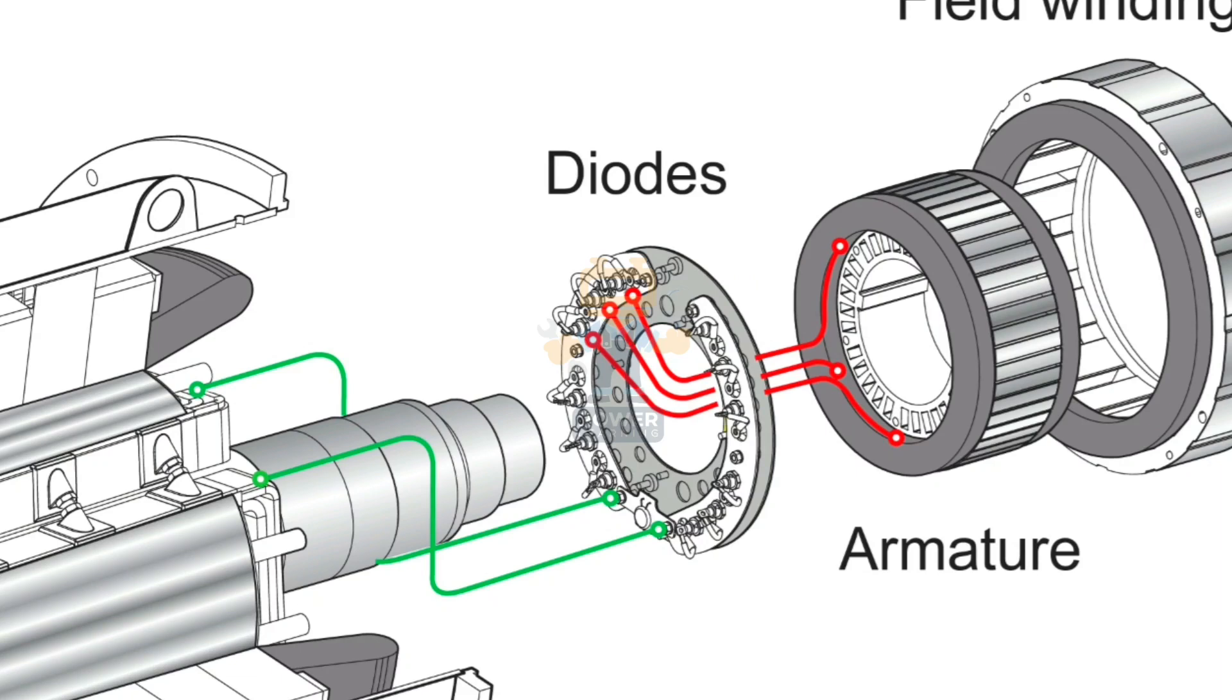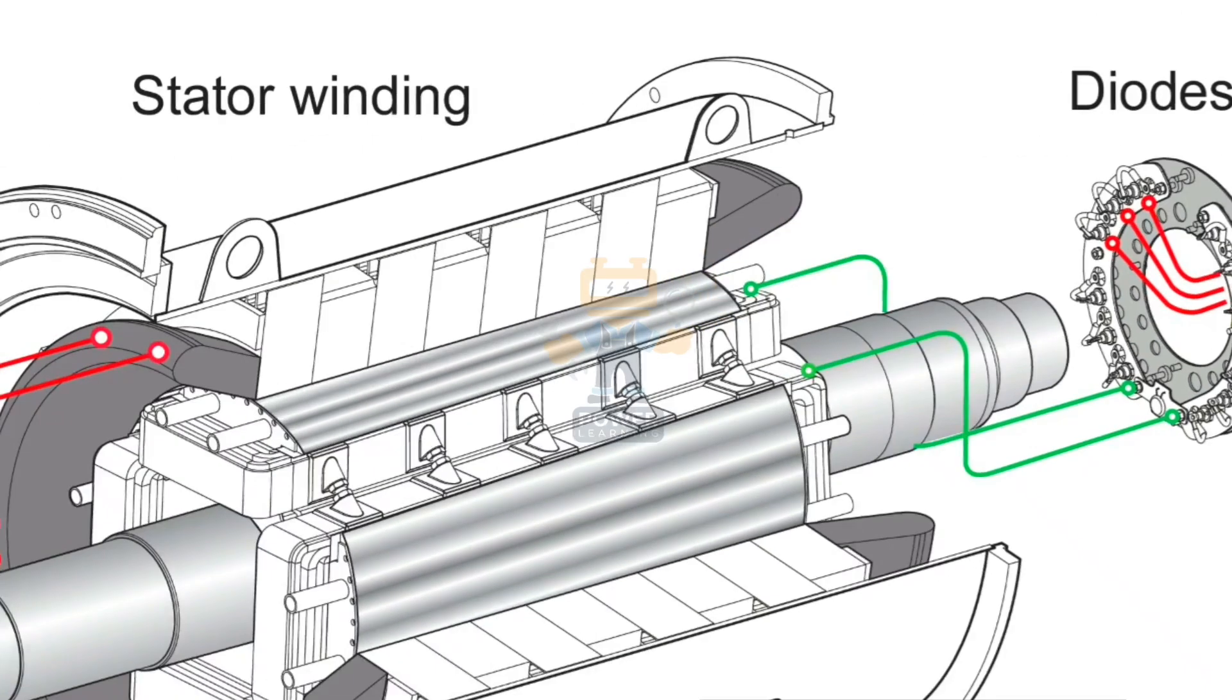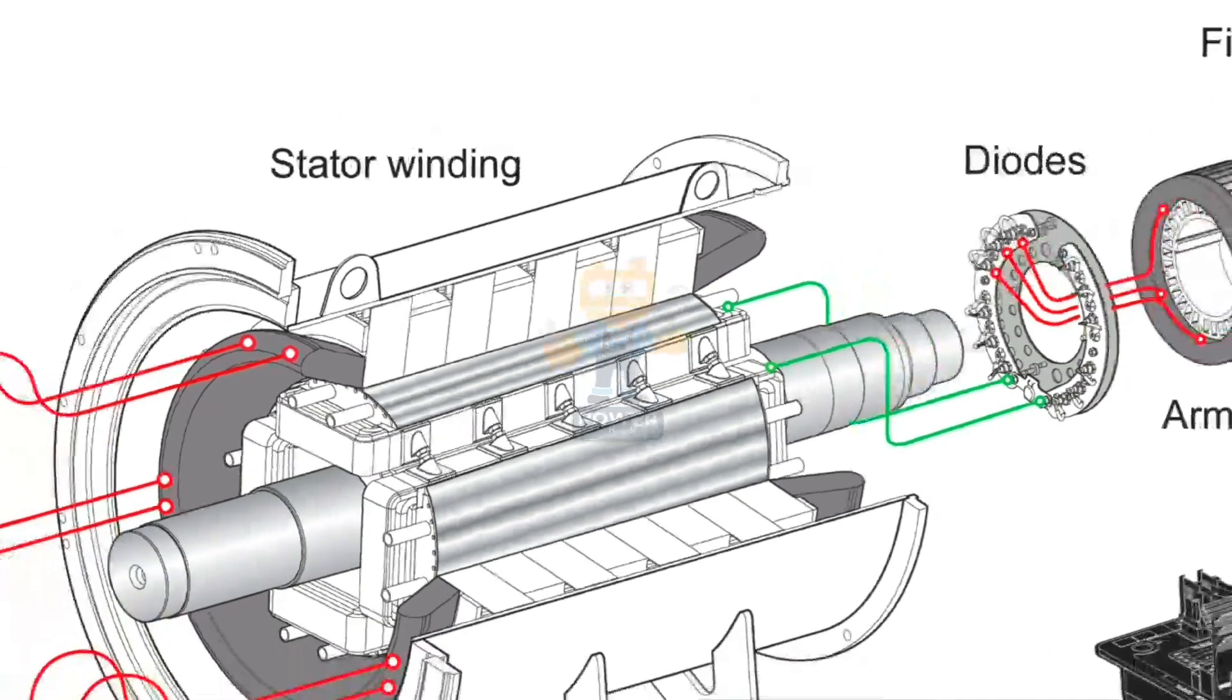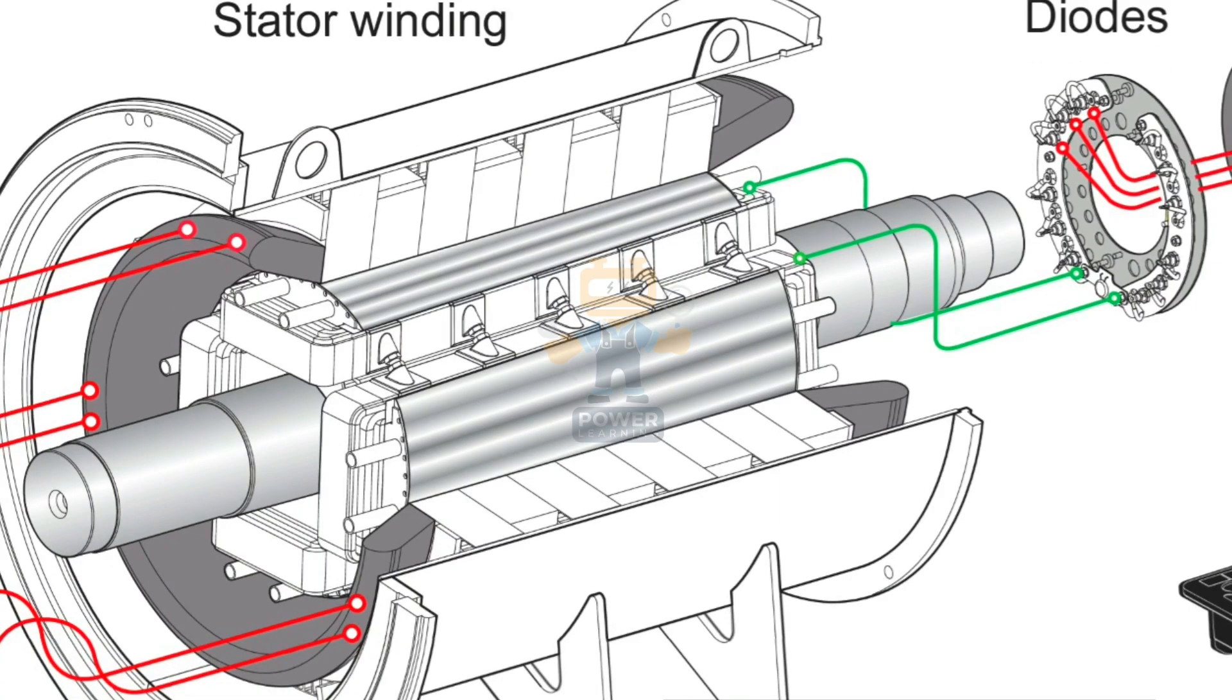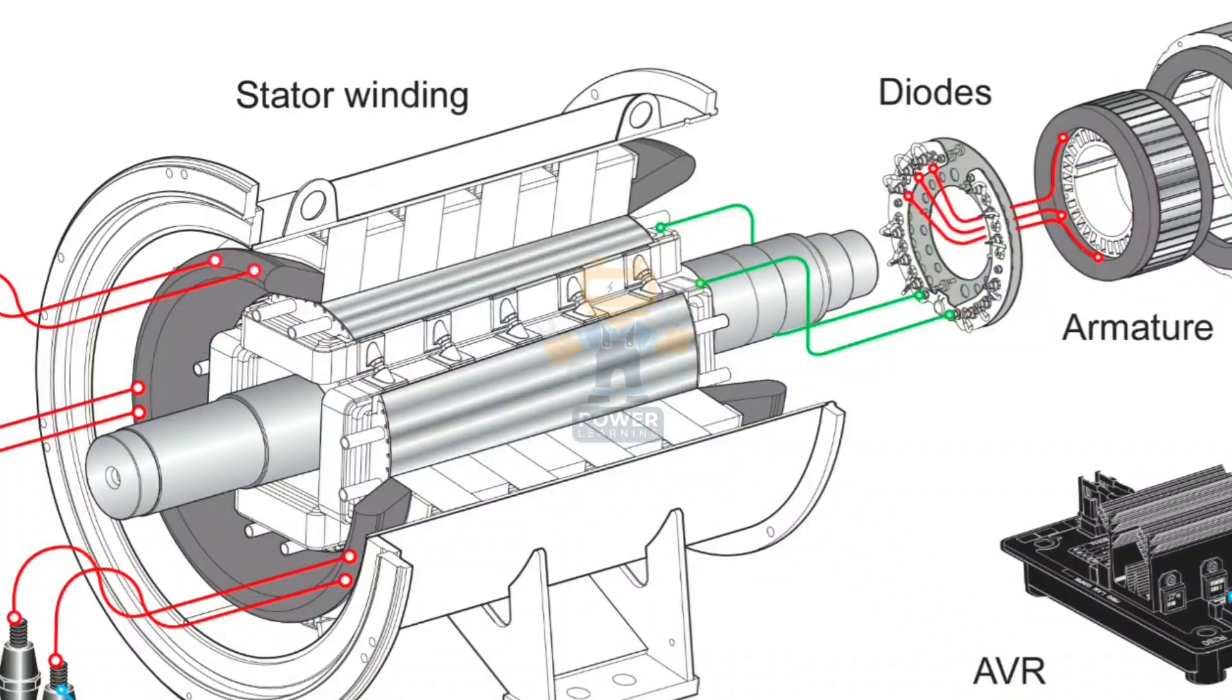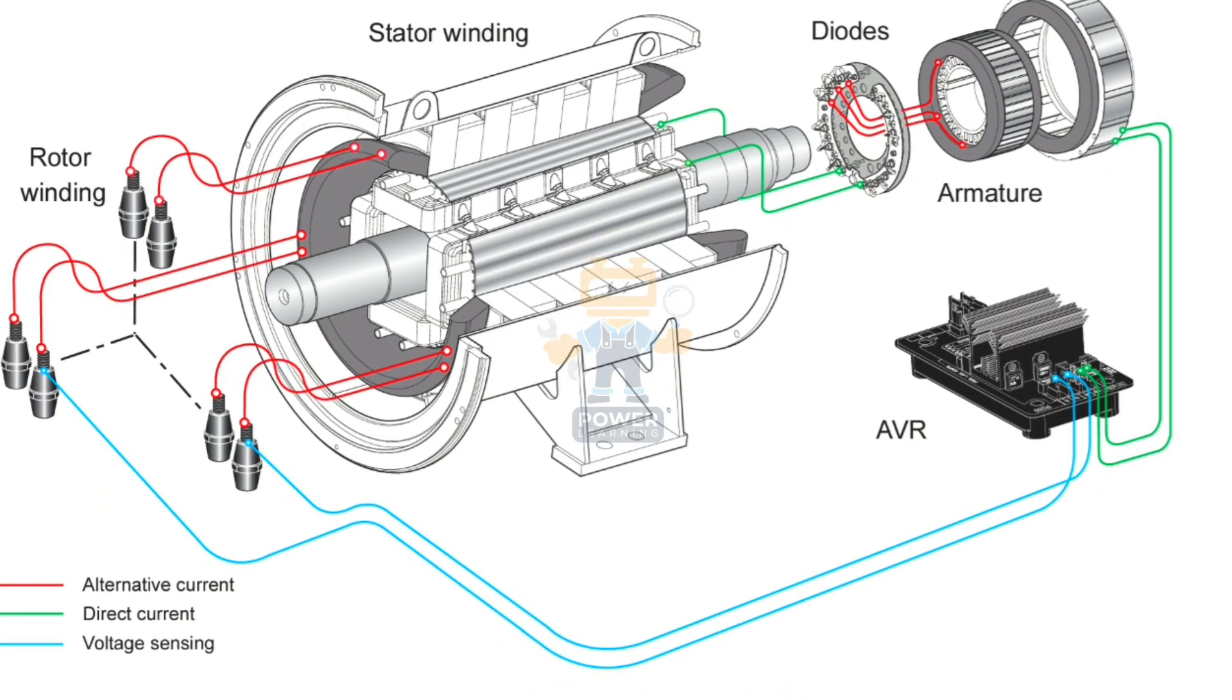Once the armature revolves inside this stationary exciter, it will produce three phases on the armature winding. We take this three-phase from armature and connect it to our diodes. These diodes will convert this AC supply into DC, and this DC goes to our main rotor. Once it reaches the main rotor, it will produce a revolving electromagnet. Once the revolving electromagnet moves inside the stationary winding of stator, electricity will be produced as per Faraday's law of electromagnetic induction.